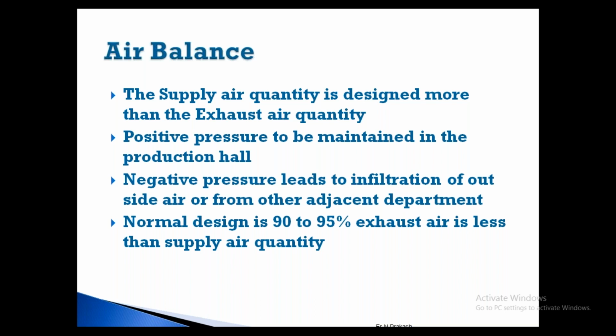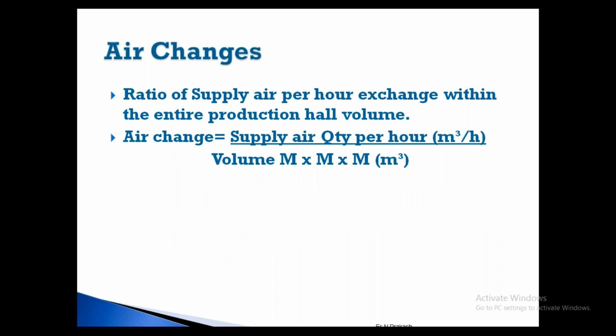This air balance is very important. Without air balance, you will face a lot of fluctuation and problems in the production. In a textile mill, at a stretch, there will be problems in the production. There will be sudden stoppage of four or five machines on one side, and suddenly four or five machines will start up due to these fluctuations. This kind of problem will happen. So, the air changes I was telling about, this is the minimum recommended air changes to maintain.